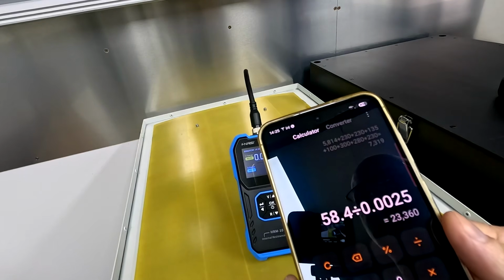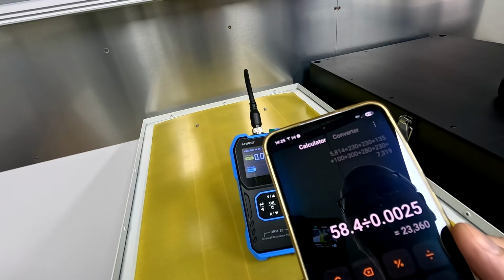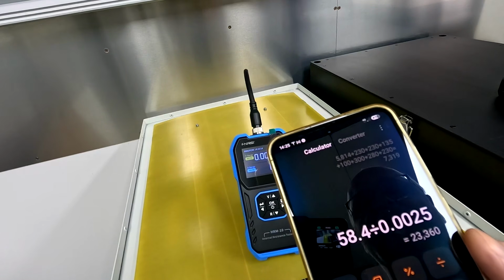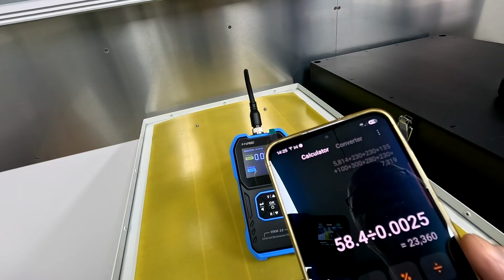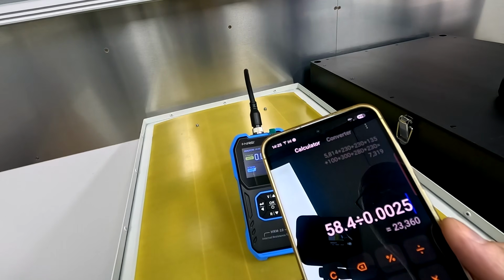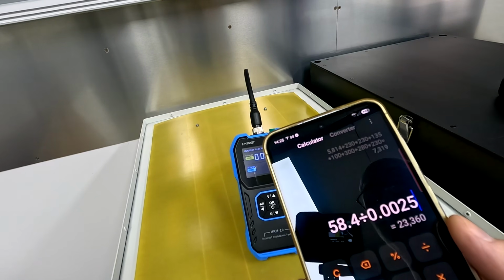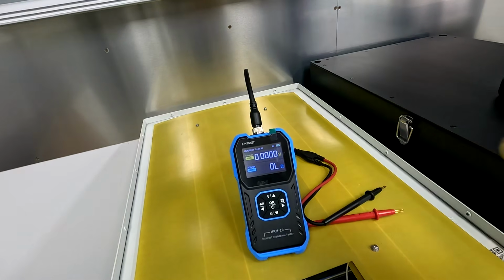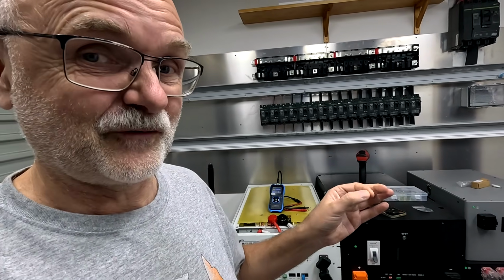To determine the maximum short current of such a battery, you also have to calculate with a maximum voltage. Battery fully charged, all cells on 3.65 volts. So the overall voltage of this battery is 58.4 volts then. If you take the 58.4 volts divided by the internal resistance of 2.5 milliohms, you're getting a bit over 23 kiloamps for such an MB56 battery. So this would be the maximum short current, of course, for such a battery.